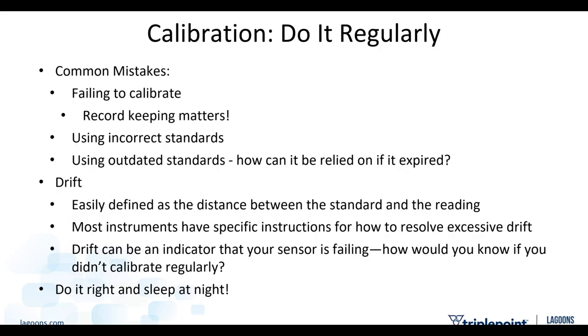And common mistakes: failing to calibrate, using the wrong standards, or using an expired standard. How can you possibly stand in front of your boss, or a judge someday maybe, and say, absolutely, that pH was 6.2, I know it was because I calibrated the meter? If you didn't calibrate the meter, how do you know it was 6.2? Maybe it was 7.3. Who knows?